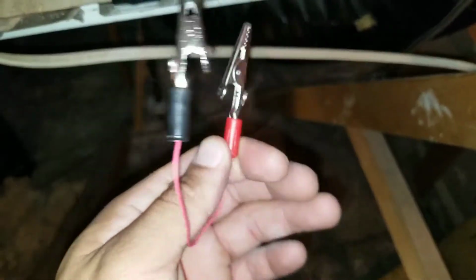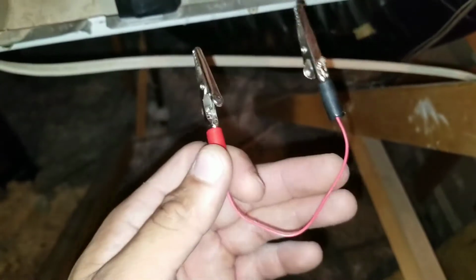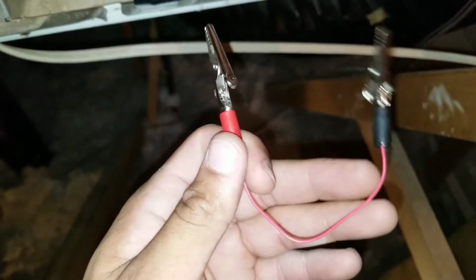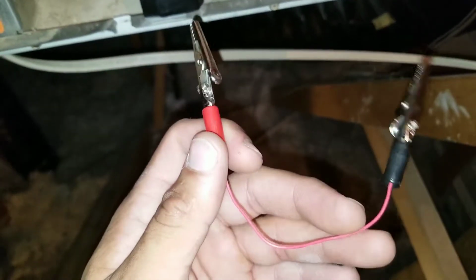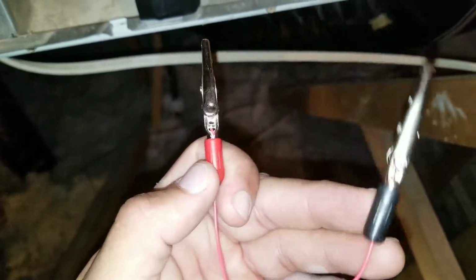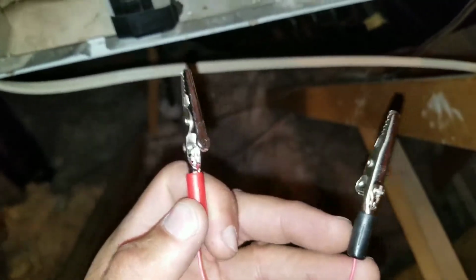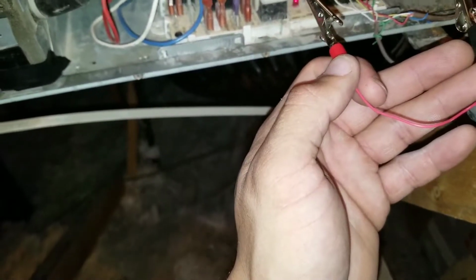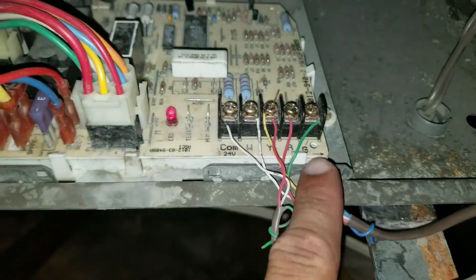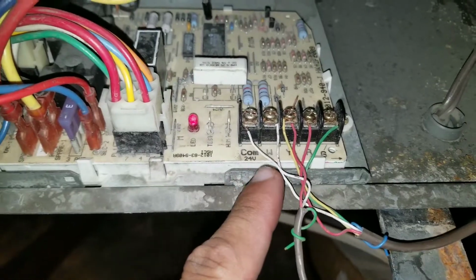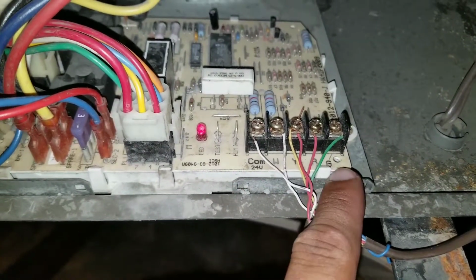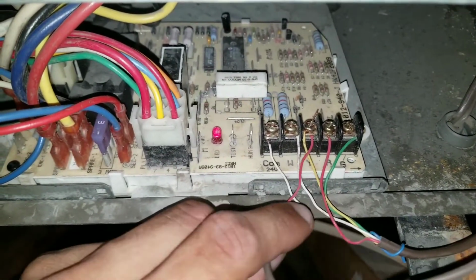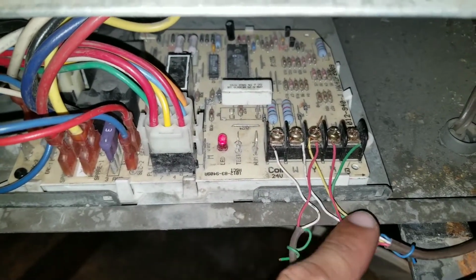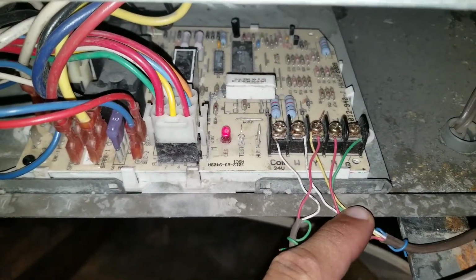Here, I bought these end leads. These are the alligator clips, and I took one of the thermostat wires that I had laying around for the 24 volt and tied them in. This is going to allow me to jump the system up here using my alligator clips. Here you can see I have my W, Y, R, and G terminals and the wires that are running to them. So the first thing we're going to do is test our blower motor.